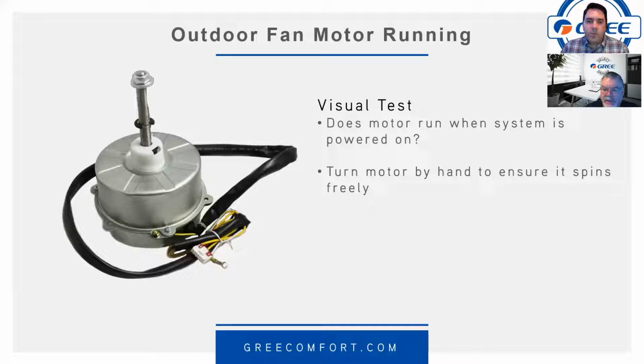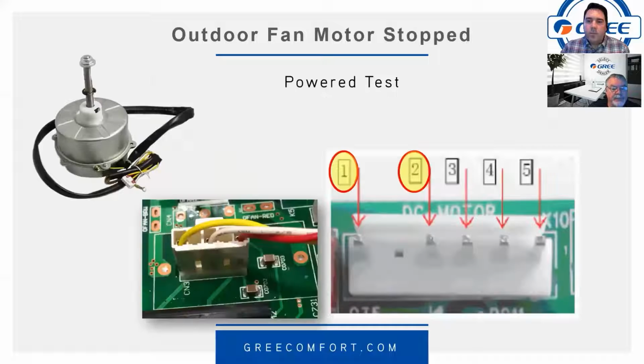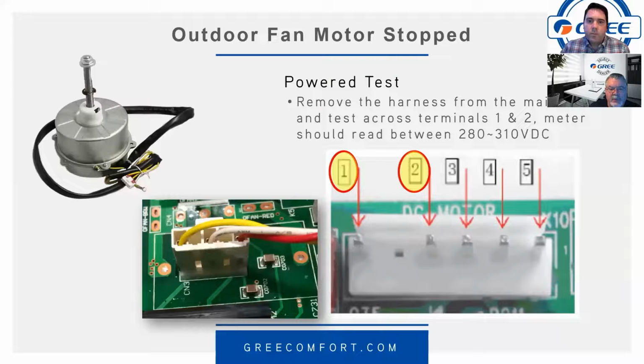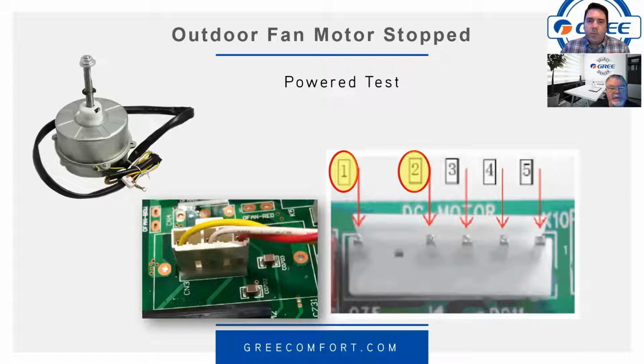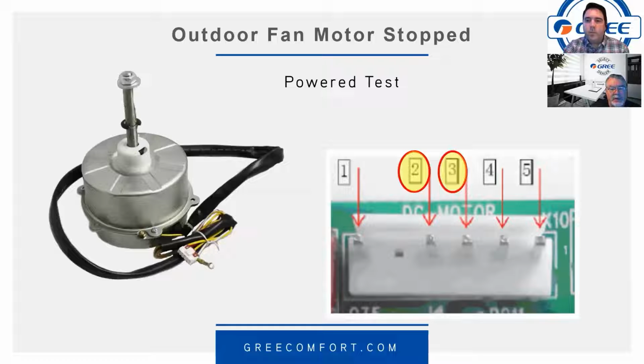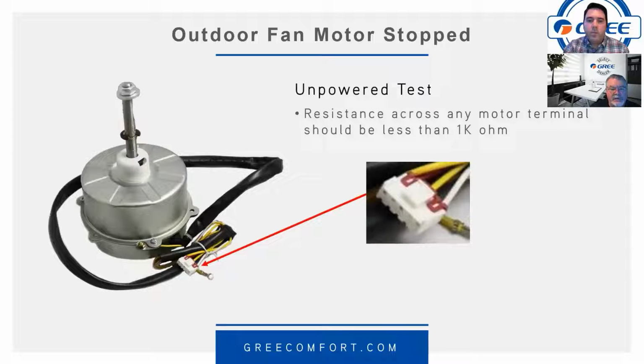Then turn system on in turbo mode. Is the outdoor fan running? If so, the motor should be good. And if you need to do a powered test, this is the terminal strip on the board, and you test terminals 1 and 2, and remove the harness from the board first, and then test these terminals 1 and 2. You should have 280, 310 volts DC across there. You can also do this powered test across 2 and 3, and you should read 15 volts DC. And then there's also the harness test, and just across any motor terminals should be less than 1 kilo-ohm.